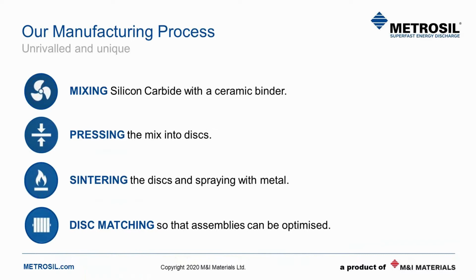First we mix silicon carbide with a ceramic binder and some additives, and we tune the recipe to meet customer requirements. Then the discs are pressed and sintered at high temperatures, and the faces are metallized to form the electrodes. There's also a 2-pack painting and curing process to form an insulated disc edge.